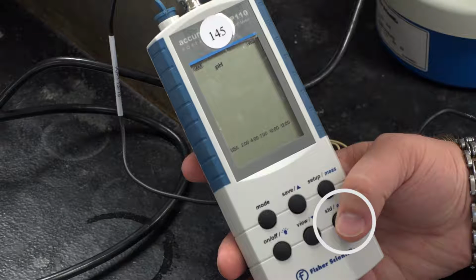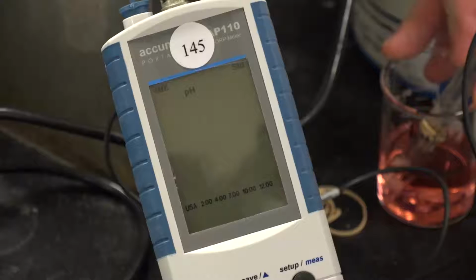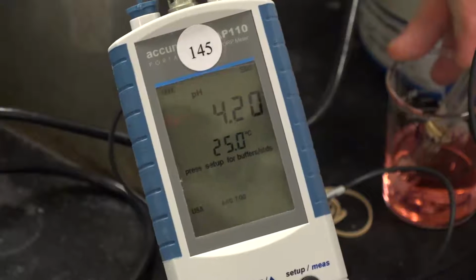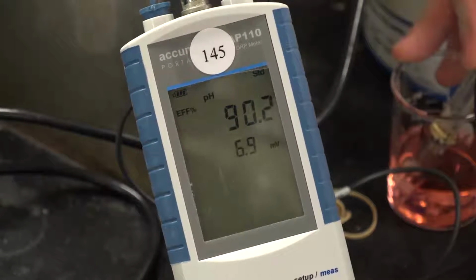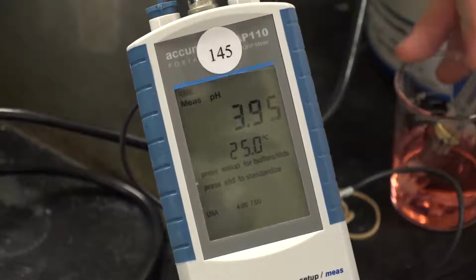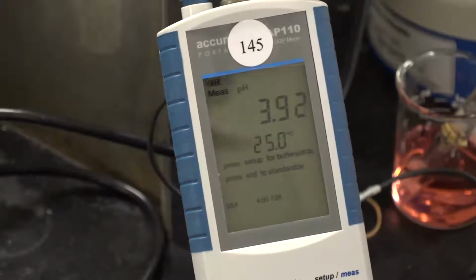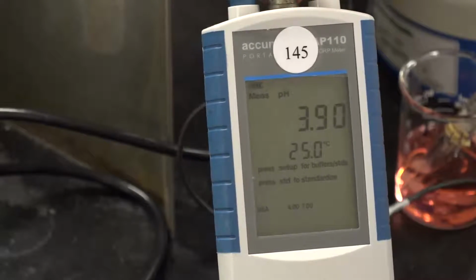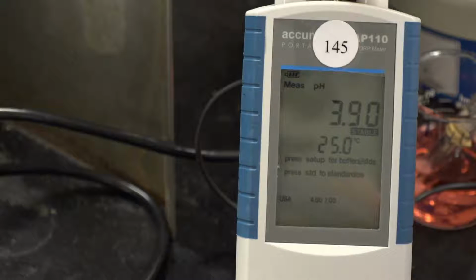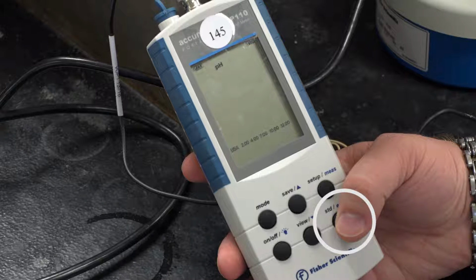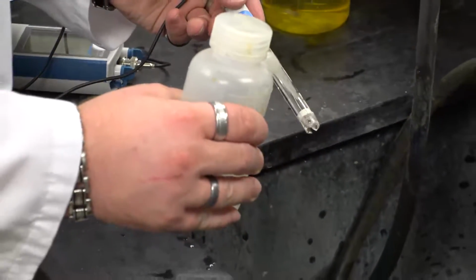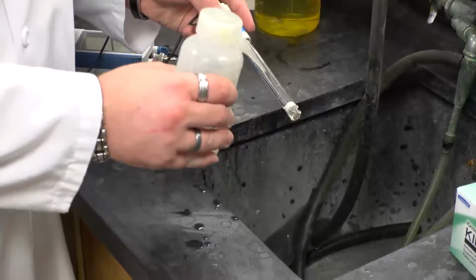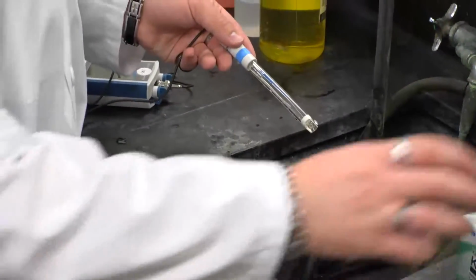While the probe is sitting in the solution, hit the standardize button on your meter, abbreviated STD/enter. On the screen, you should now see STD appear. From here, allow the pH value to reach a constant reading. With a little variation over 30 seconds, you should also see stable appear on your screen. Once the stable indicator appears, press the STD/enter button again. After removing your probe from the pH 4 buffer solution, rinse it with a little DI water, then blot dry. Place the probe into the pH 7 buffer solution.